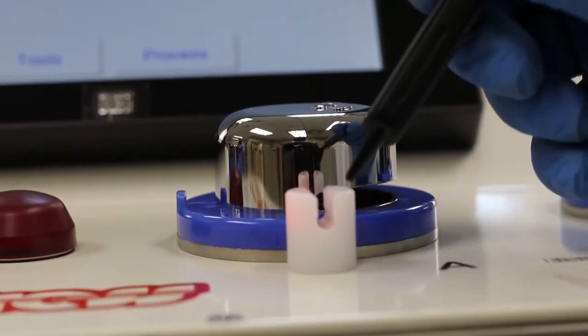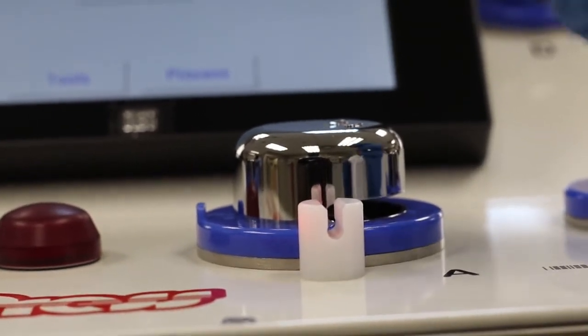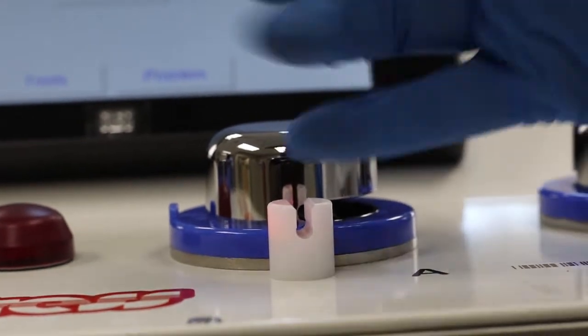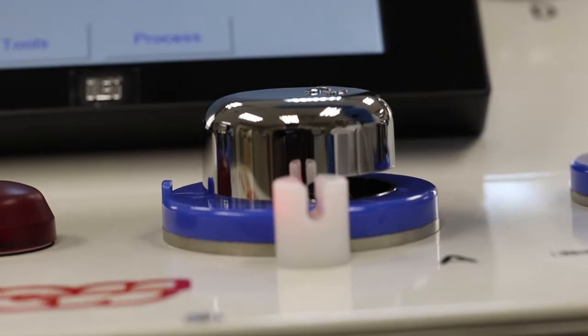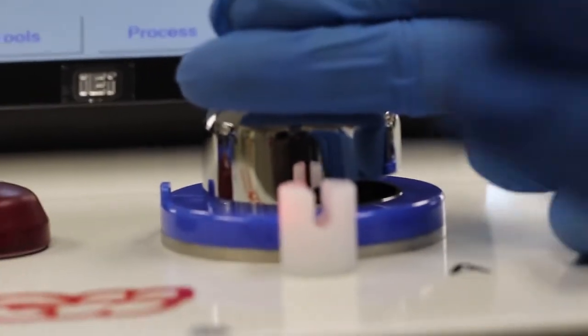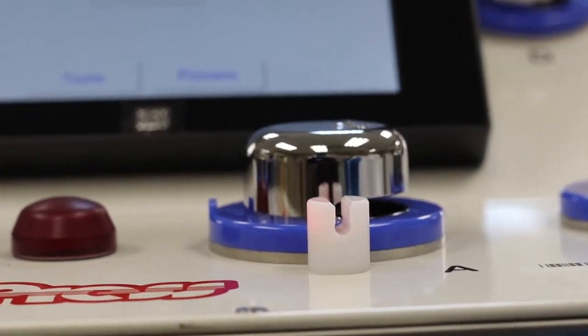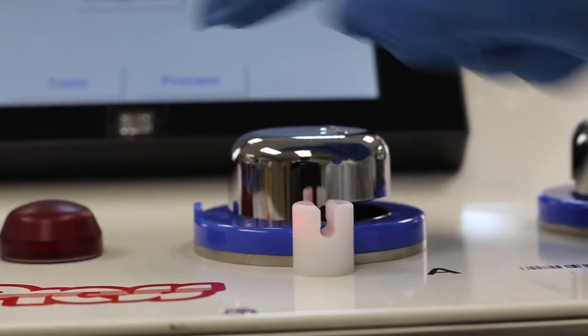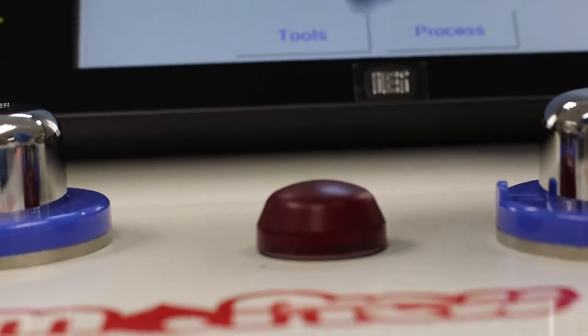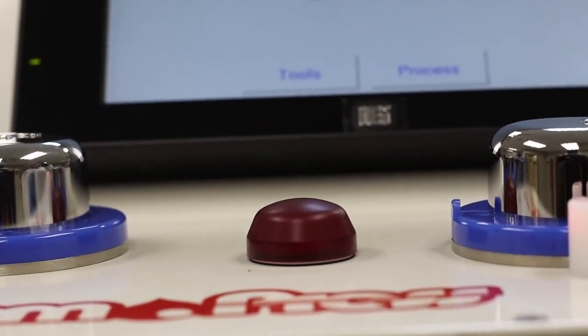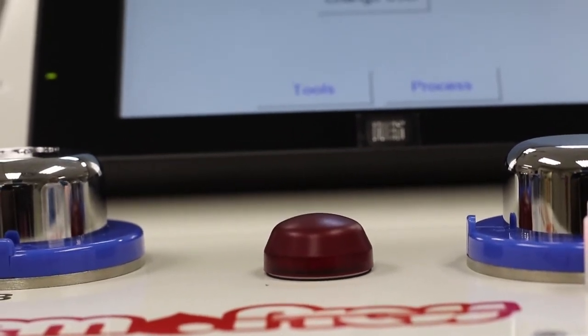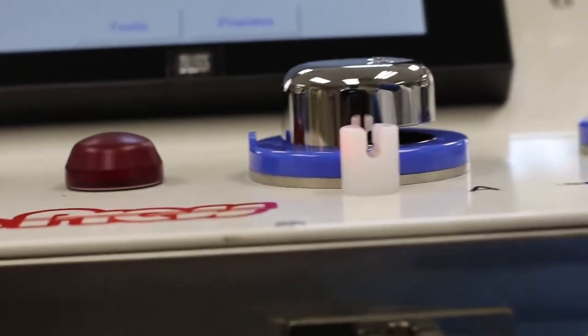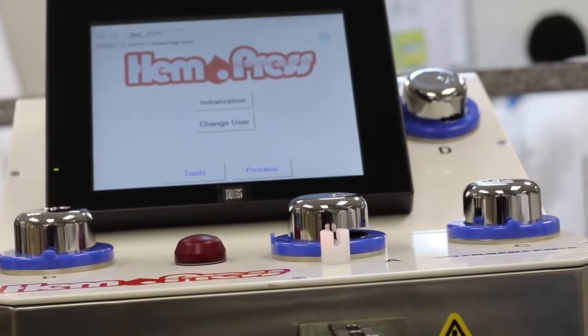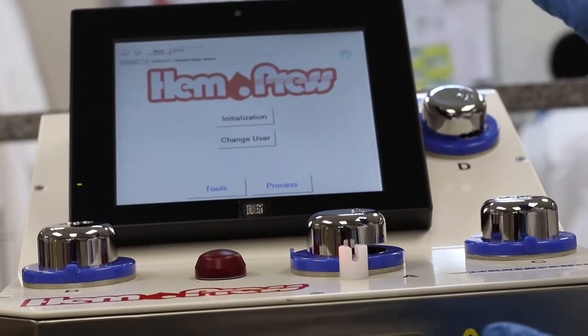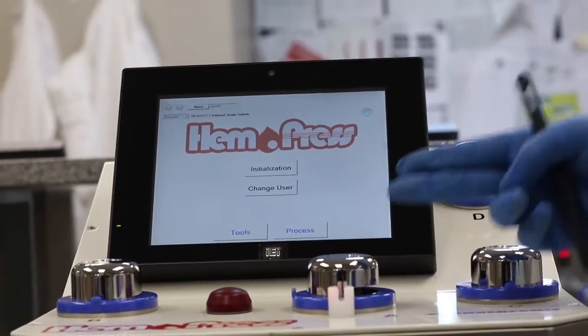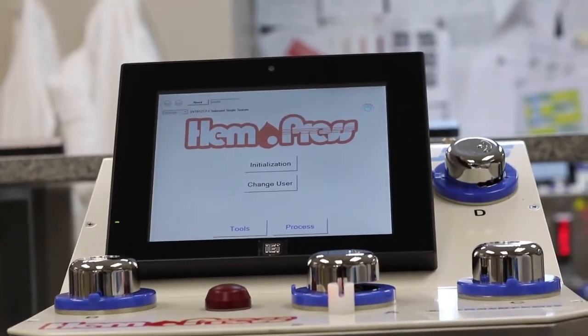Our intelligent sensor will alert you if any red cells pass through your sensor. If it detects a change in color, clamp A will immediately close. Your presser plates will pull back 3 millimeters to draw back the red cells that might have pushed into your tubing. The alarm will sound, a visible and audio alarm, and you will have a pop-up on your screen to alert you that there's possible red cells in the tubing. Should you see that the red cells are all back in the bag, you just press continue and it will continue your process. I will deliberately push red cells up when we process to show you how it closes and pulls back to put the red cells back into the bag.